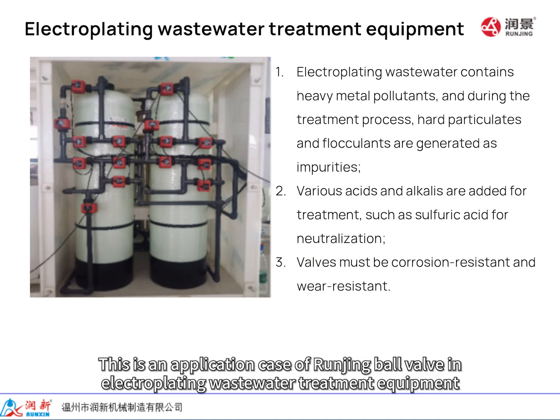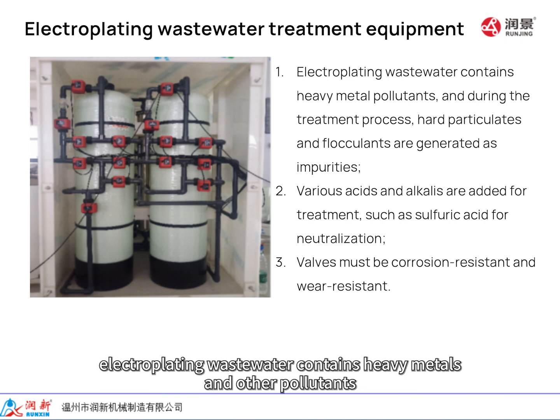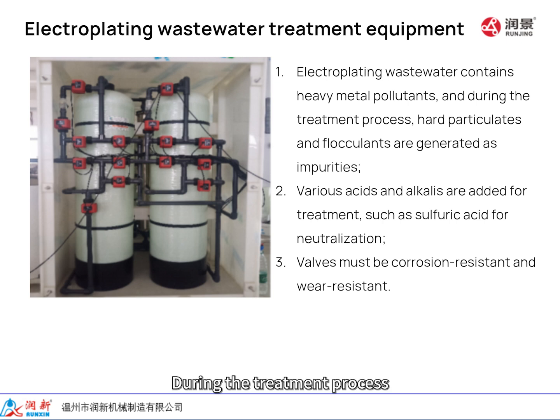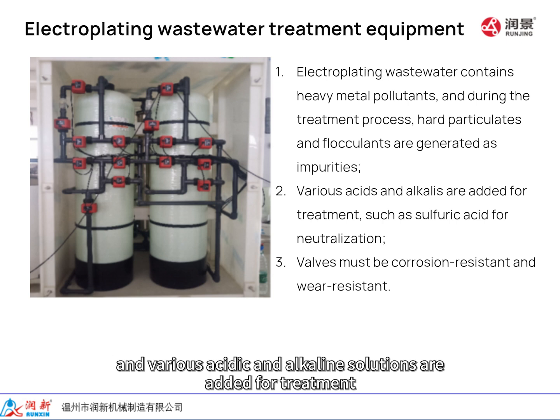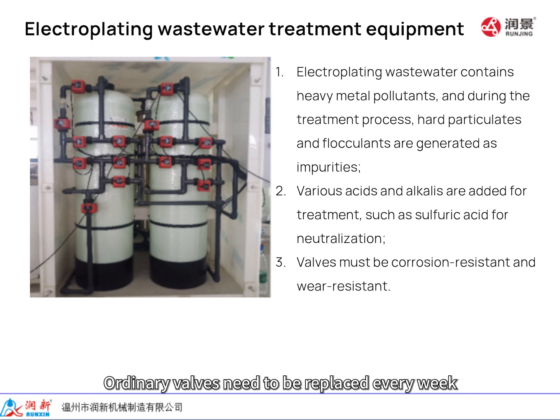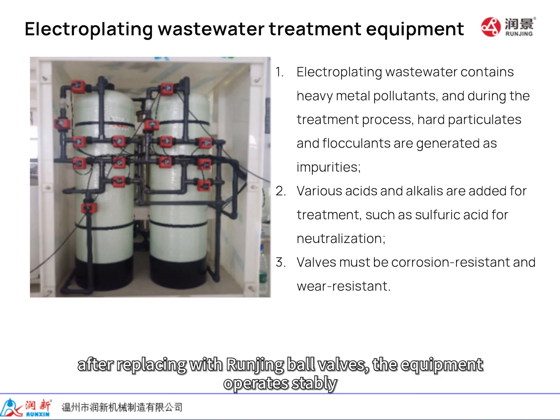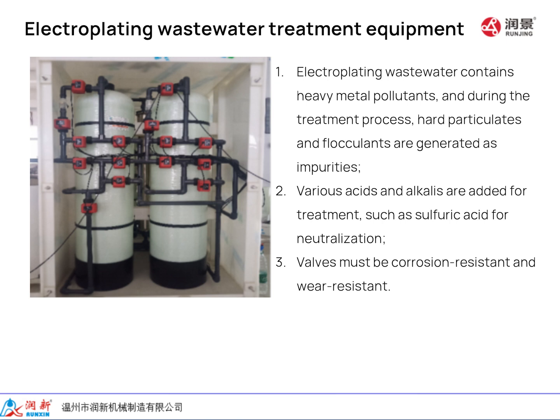This is an application case of Runjing ball valve in electroplating wastewater treatment equipment. Electroplating wastewater contains heavy metals and other pollutants. During the treatment process, hard particles and flocculants are produced, and various acidic and alkaline solutions are added for treatment. Ordinary valves need to be replaced every week. After replacing with Runjing ball valves, the equipment operates stably.